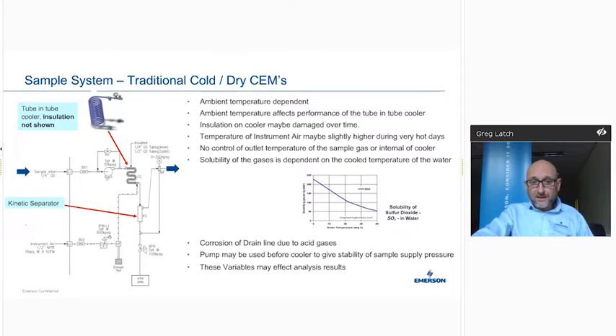Going down through the system, then obviously you're now heading off to a kinetic separator in this particular application, going down for all your liquids. And then off up to the far right, you're going through a particulate, the final point of, let's call it filtering before your standard analysis system. You've got just, for example, like a Genie filter or particulate catching device in your sample handling. Obviously, you do have to be very aware of the aspects of liquids in your process streams, and in saying that you will have potential knockout of some of those components of interest from a dew point of view. So the graph there just represents, for example, sulfur dioxide solubility in water. And obviously we're knocking out water, so you do have to be aware of that.